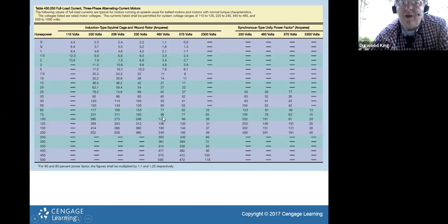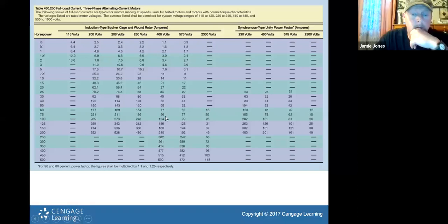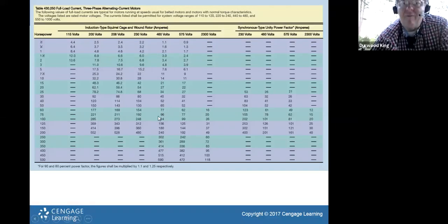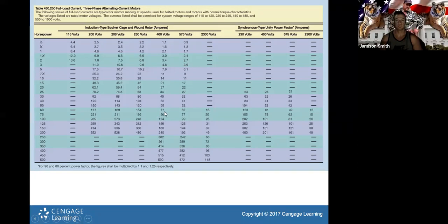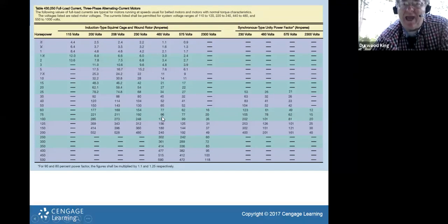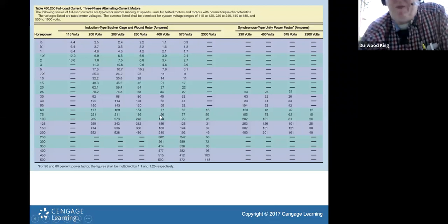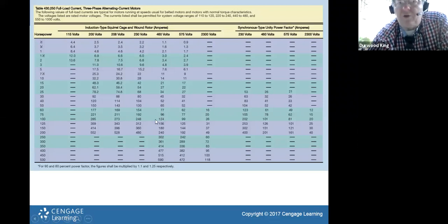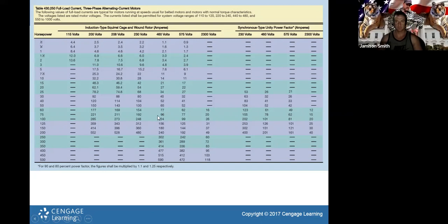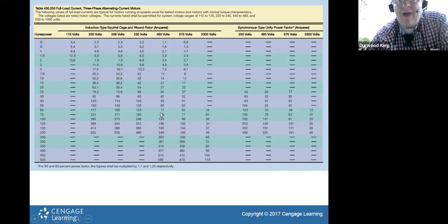Okay, so that would be your amp draw under full load. Can y'all see the 96 there? Now that should line up with your nameplate also. I can tell you these numbers are middle of the road numbers that represent different brands. So you may find a slightly different number on a motor, but it's not going to be far off of that on a nameplate. It's going to be very close to that.